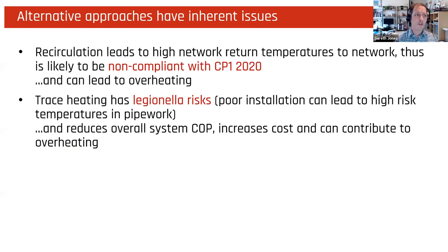I'm not going to go into that here. Alternative approaches have inherent issues on heat networks. I won't go into that. Recirculation really wouldn't be advised. And trace heating, in practice, we've seen a number of issues around Legionella, somewhat ironically, where poor installations lead to higher temperatures being maintained in pipework. And it also leads to overall higher energy use.